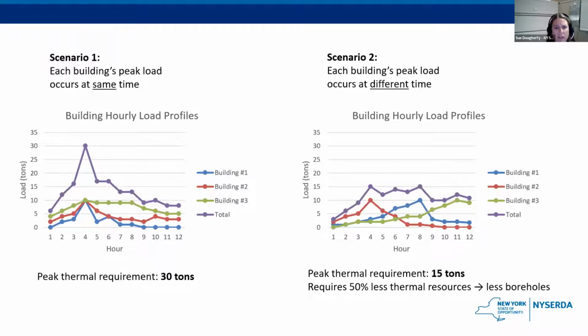This is a simplified example of why a district system might offer an advantage to three buildings. In the graph on the left, three buildings with different operating profiles each peak at the same time, at hour four, so all loads aggregate to produce a peak of 30 tons. In this case, you'd still need 30 tons of thermal resources to heat those buildings.